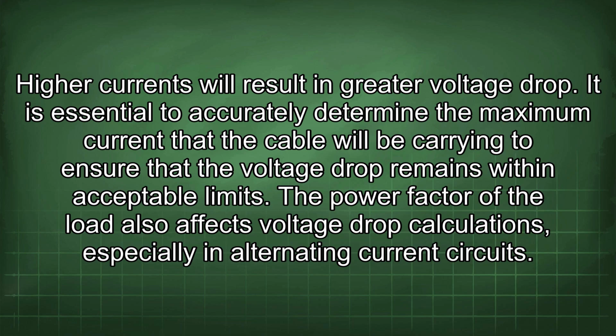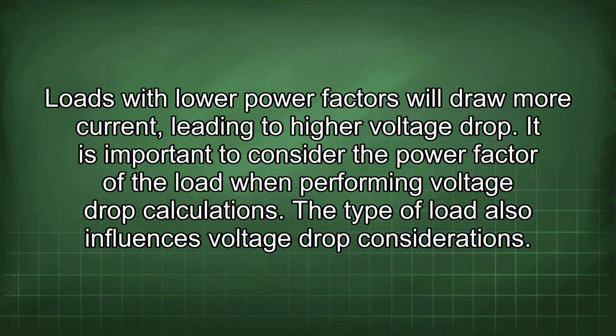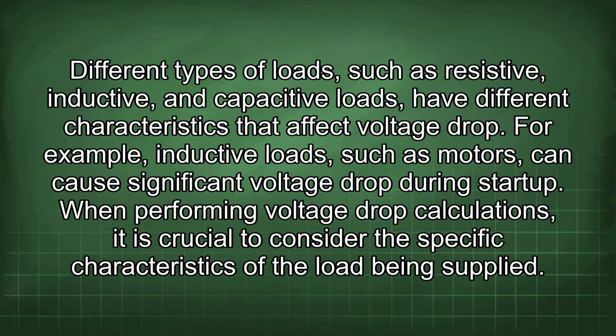The power factor of the load also affects voltage drop calculations, especially in alternating current circuits. Loads with lower power factors will draw more current, leading to higher voltage drop. It is important to consider the power factor of the load when performing voltage drop calculations. The type of load also influences voltage drop considerations. Different types of loads, such as resistive, inductive, and capacitive loads, have different characteristics that affect voltage drop. For example, inductive loads, such as motors, can cause significant voltage drop during startup. When performing voltage drop calculations, it is crucial to consider the specific characteristics of the load being supplied.